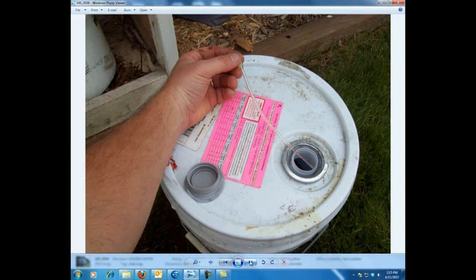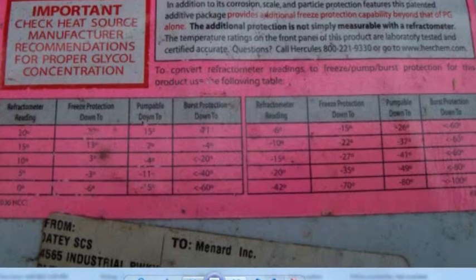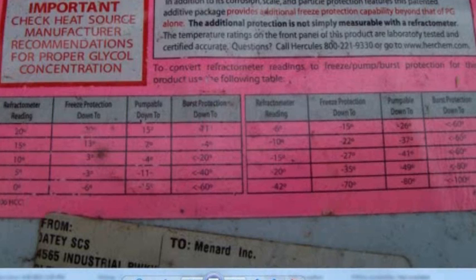The refractometer is merely telling me that I have a zero to two degree freeze point. That is not the complete picture. What I need to do is go to the manufacturer and consult the sticker associated with this product. This manufacturer of propylene glycol provides a correction chart, so if you're using a refractometer, there's a compensation adjustment to apply.